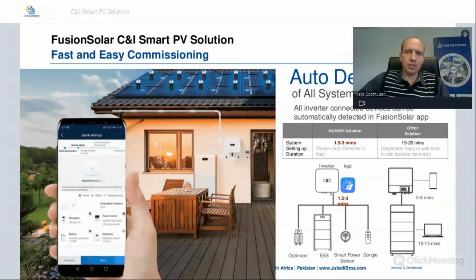Continuing with fast and easy commissioning. So, auto detection of all system devices. All inverter connected devices can be automatically detected in the Fusion Solar app. Because of this automatic detection, the commissioning would be between 1.5 and 3 minutes, whereas in other solutions where the communication between devices is not automatic, you have to specify each one. It can take you between 15 to 20 minutes.